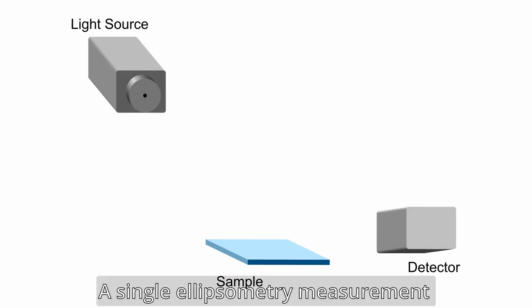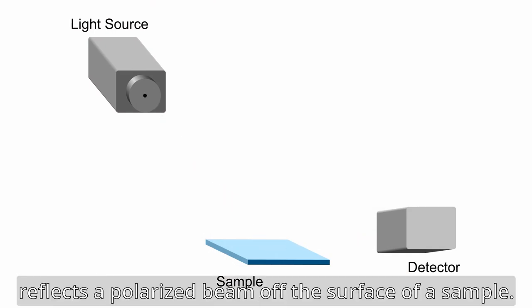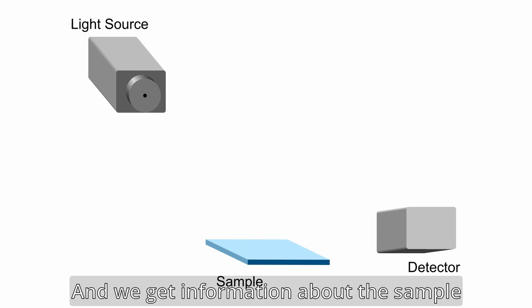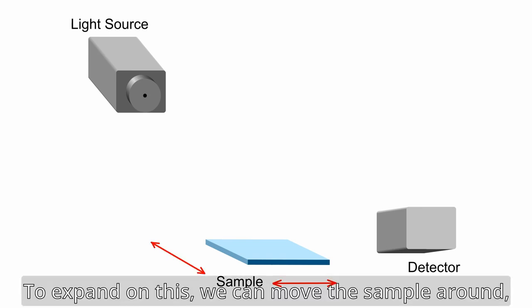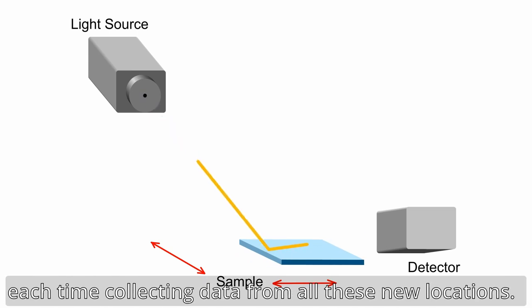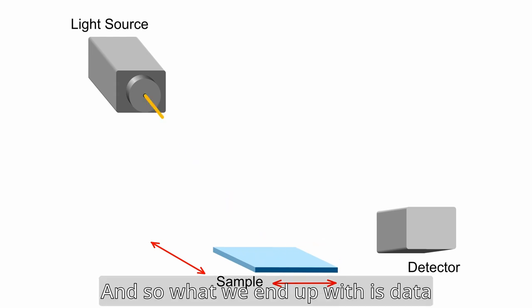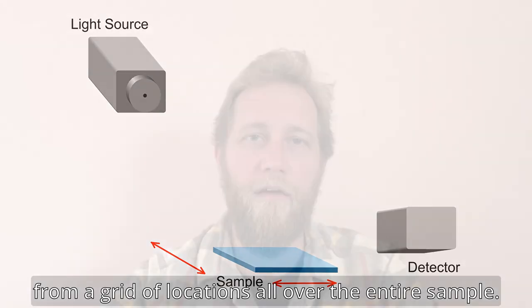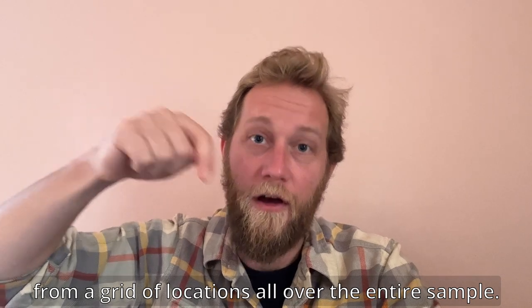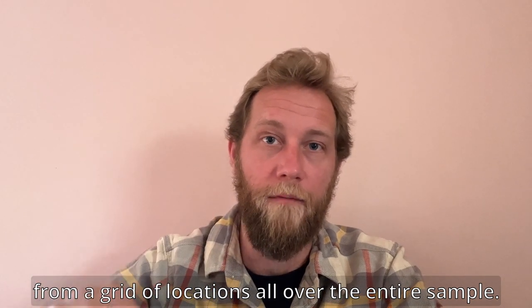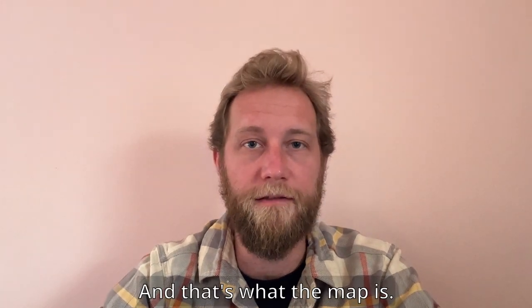A single ellipsometry measurement reflects a polarized beam off the surface of a sample, and we get information about the sample from where the beam hit it. To expand on this, we can move the sample around, each time collecting data from all these new locations. What we end up with is data from a grid of locations all over the entire sample — and that's what the map is.